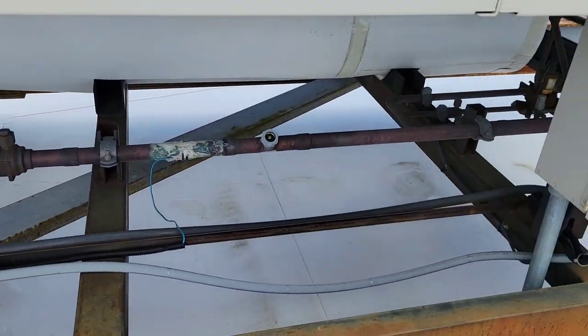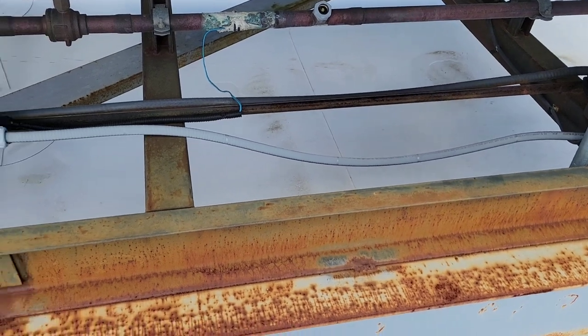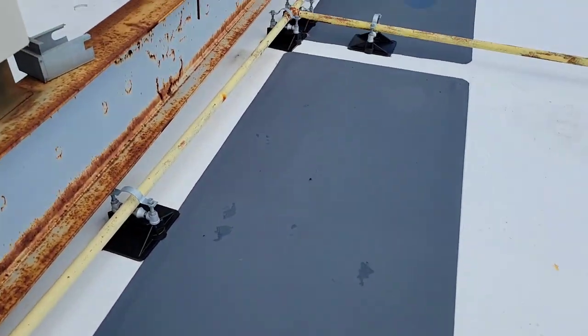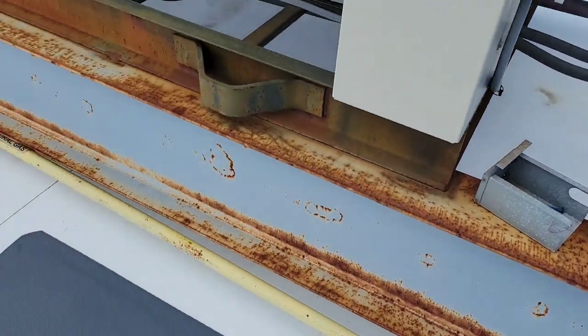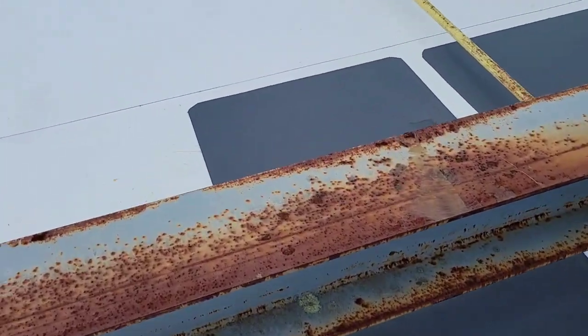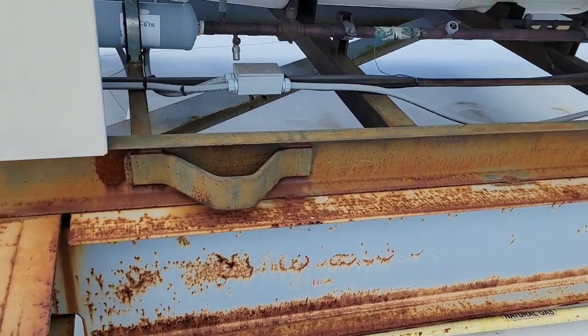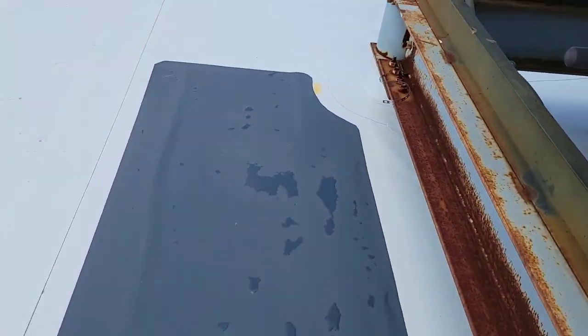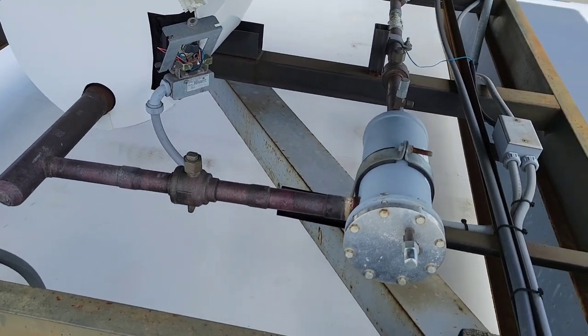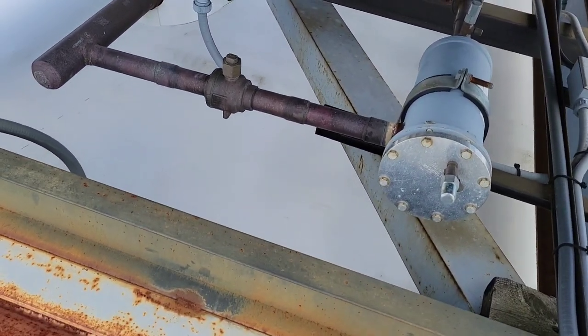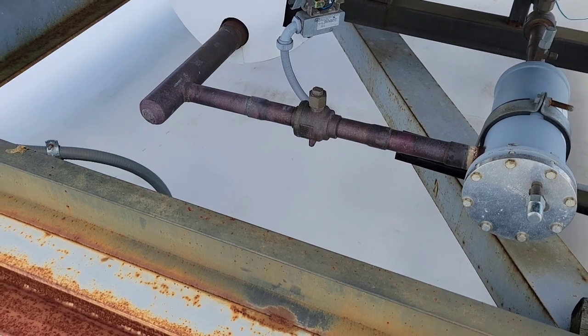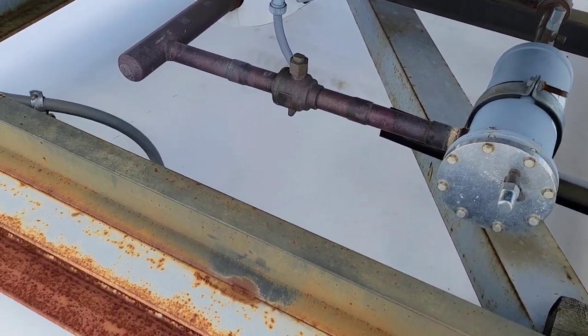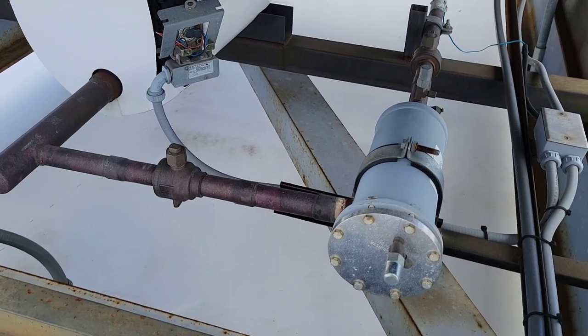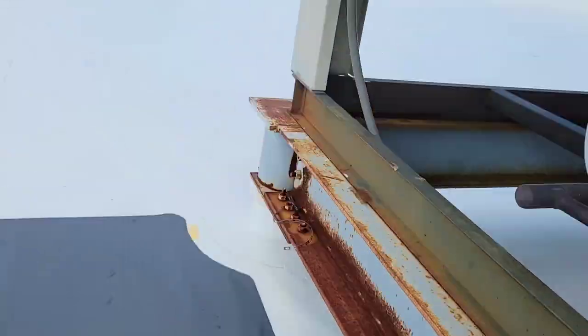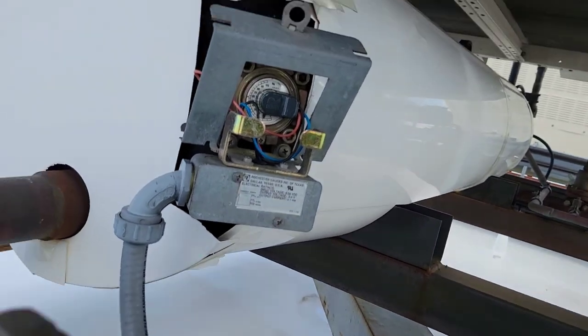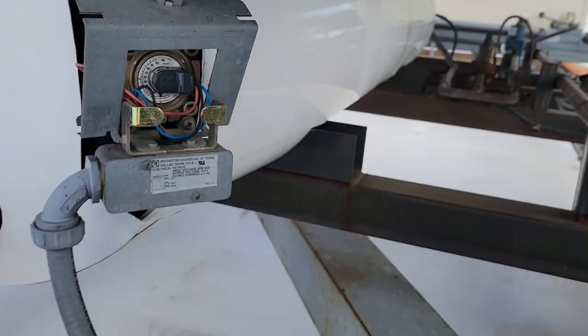And you have to stick to it. Even if, like right now, everything screams to me that more than likely the TXV screen is the problem. Why don't I just jump and do that? Because there have been countless times where if I did that, the rack would have gone down as soon as I walked away, or I wouldn't have found the issue. A lot of the time you've got to follow the procedure, even if you think you might know, because a lot of the time I think I know and I don't. So we have a sight glass over here, and we see it's around 10%, okay?